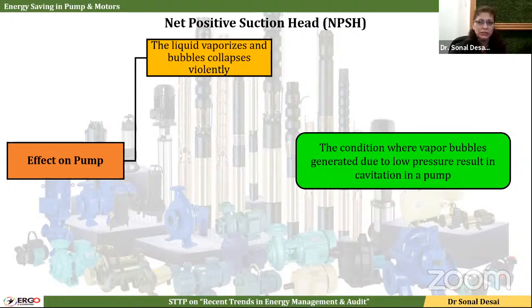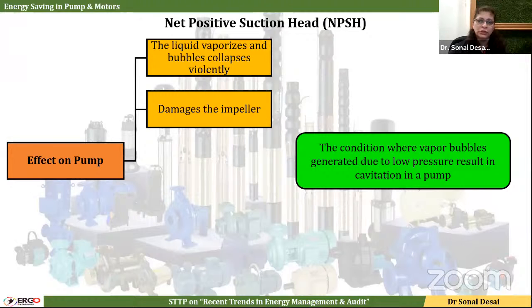One more word which is always coined is NPSH, net positive suction head, and that is ultimately related to cavitation in the pump. Cavitation is a phenomenon when the liquid gets vaporized, forming vapor bubbles. It is called cavitation. That normally happens when the liquid pressure drops below the vapor pressure. So it should not occur, otherwise that vapor formation is always harmful because the pump is not meant to handle vapor.